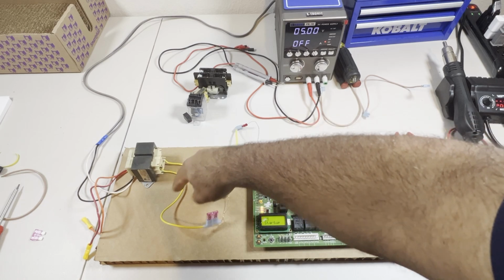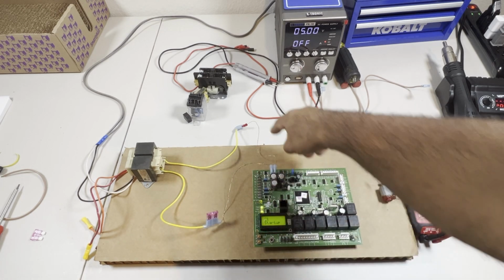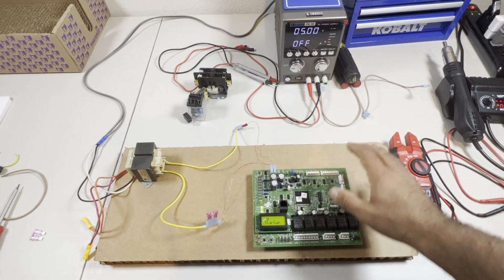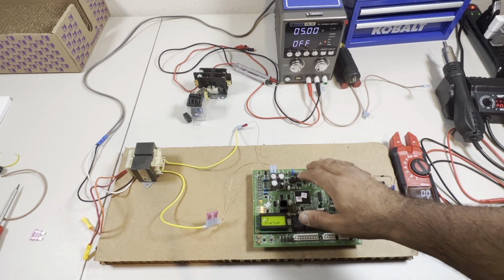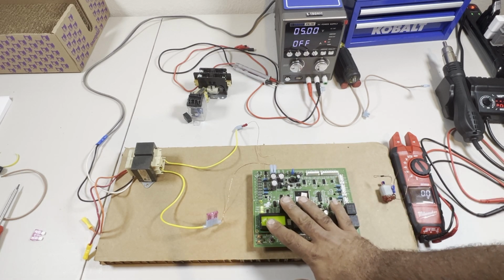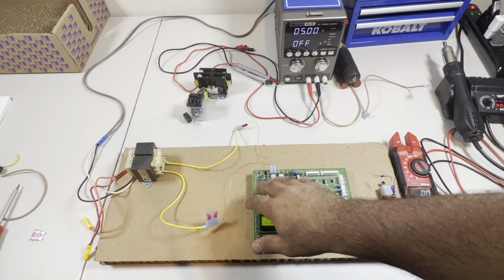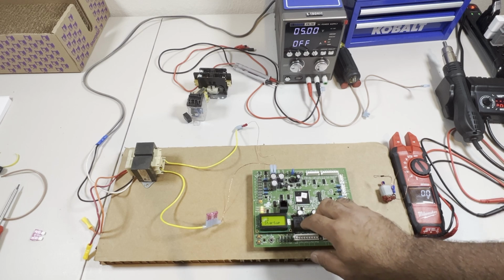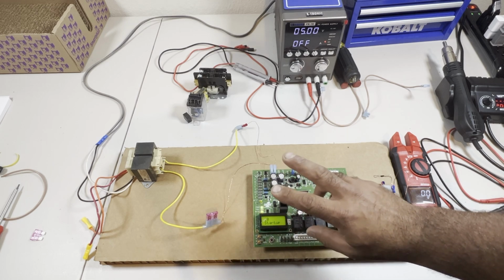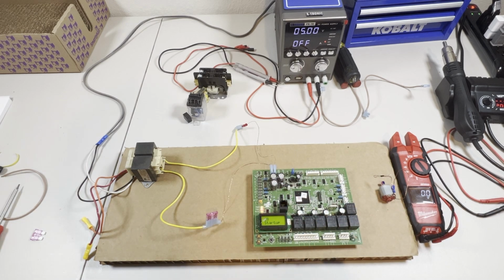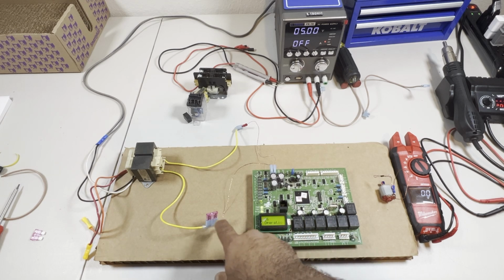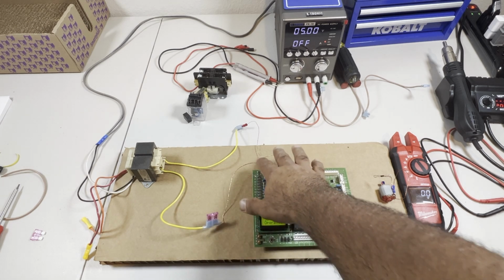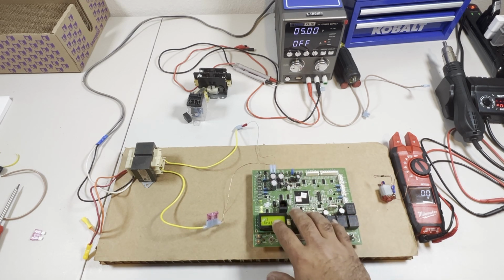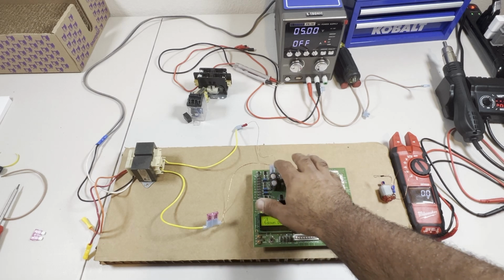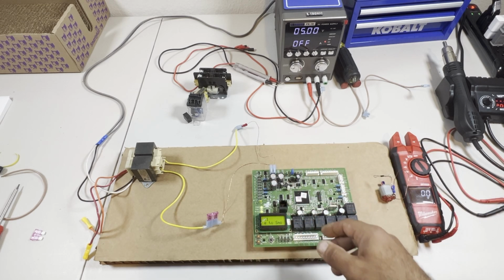Electrons coming out of the transformer, traveling into the board, goes back in here, everyone's happy. Now, according to Ohm's law, the higher our resistance, the lower the amperage is going to be. Amperage and resistance are always working opposite of each other. That's why the fuse is not blowing, wires are not melting, everything is good. This board has a very high resistance if you check these terminals with the ohm meter.